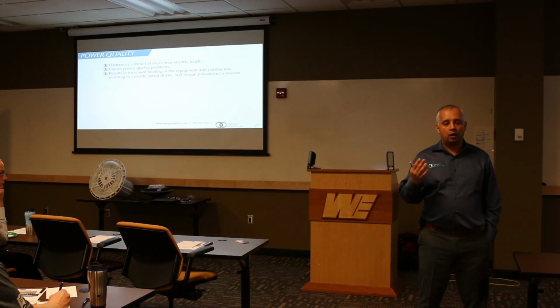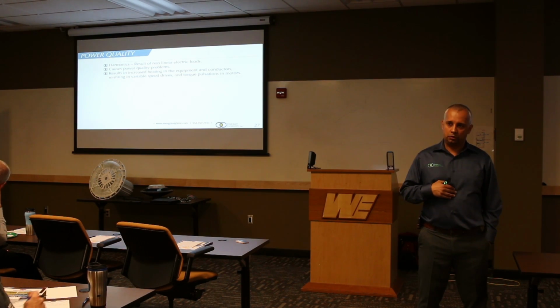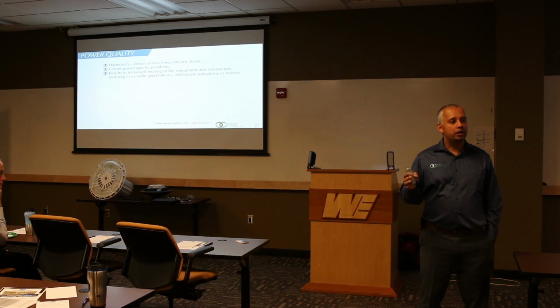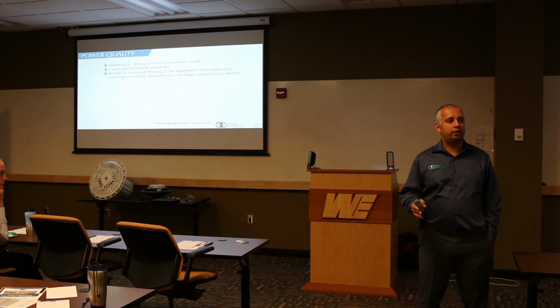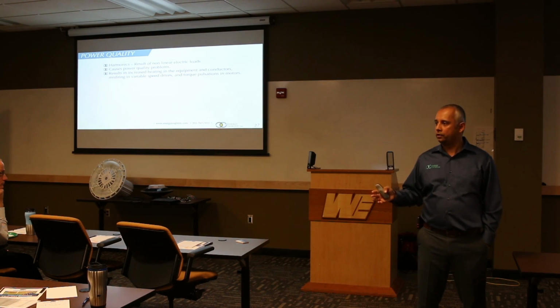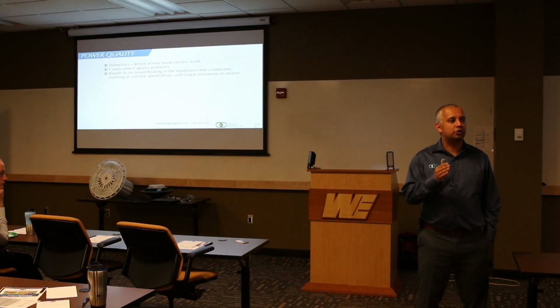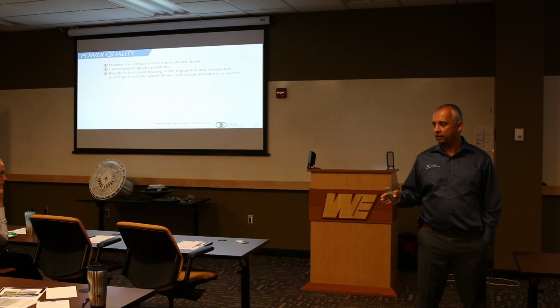A lot of people ask, if I correct power factor, will I save energy? No, you won't. Power factor correction is a cost reduction technique, not energy savings. Sales tax exemption studies will not bring you energy savings - they will bring you cost savings. So if somebody comes in and tells you to install a black box that's going to save you energy because it's power factor correction, that's not happening.